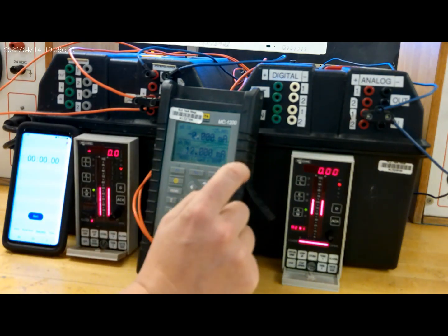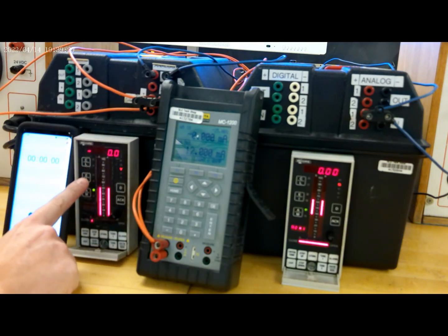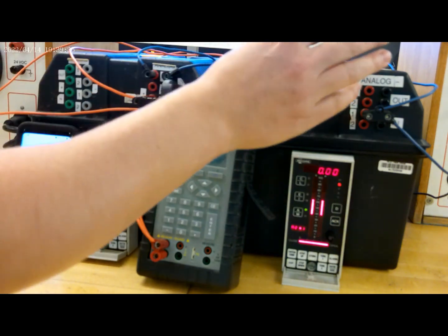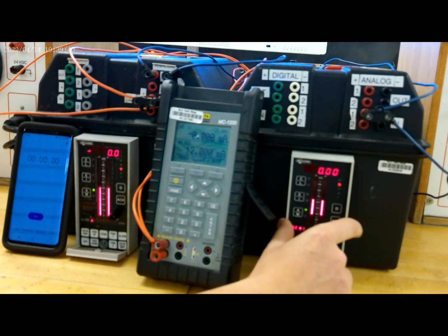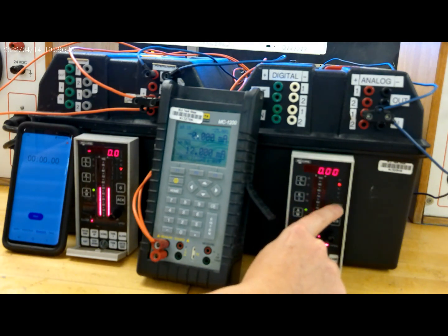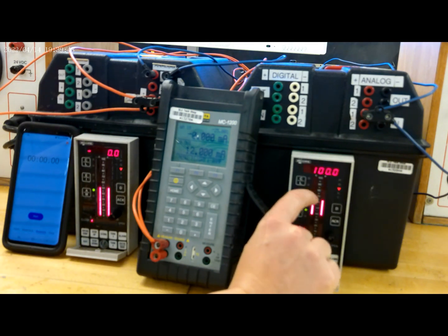Now I'm going to make a minus 20% error on this controller, which as soon as I do that, it's going to inject that ramp rate into this controller. This controller has a set point right now of 0, as we saw earlier on the board, and we are going to watch the valve output.